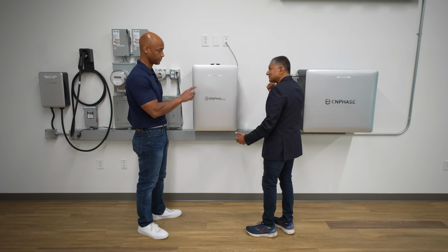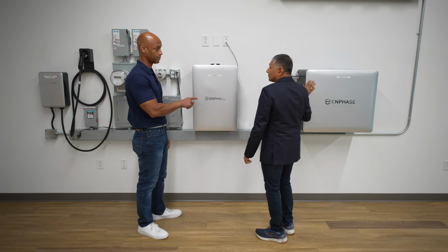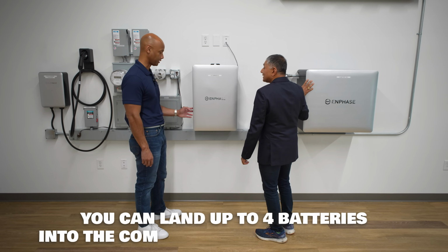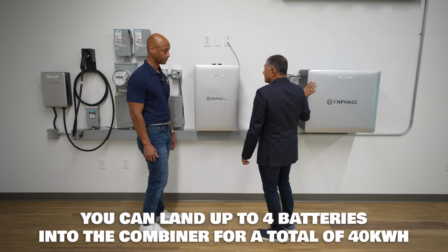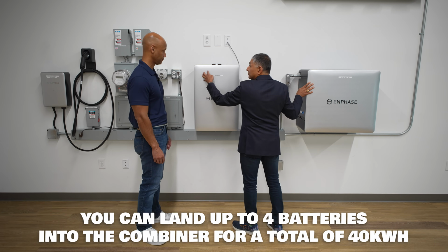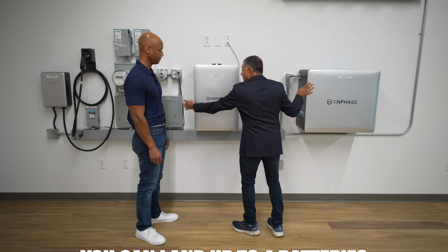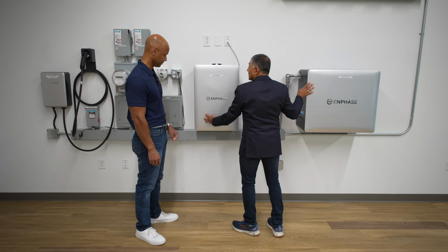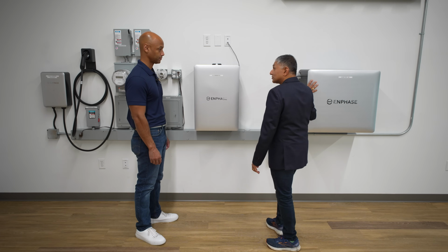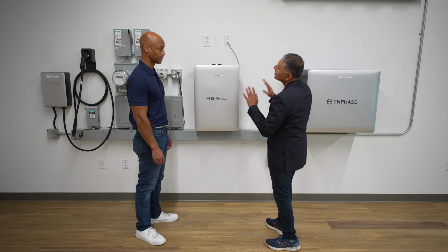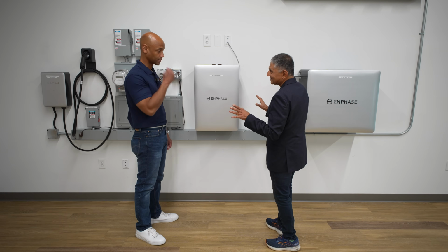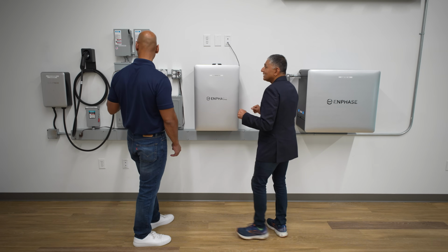That's up to 40 kilowatt hours, so up to 4 batteries, landing right into the combiner. You can land 4 20-amp circuits of PV, and up to 40 kilowatt hours of batteries in here. In fact, you can go even higher when using PCS. I also notice you have an EV charger here now.